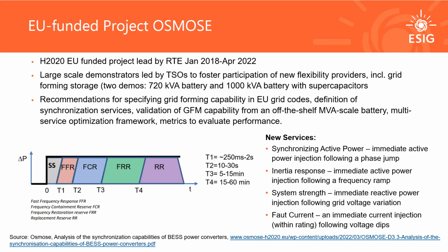Jumping to the EU-funded project OSMOSE, they also have specifications for grid forming, on a plant level. But I think what's interesting here is that they identified what they call synchronization services. These are some of the services that are currently provided by synchronous generators and will no longer be there when synchronous generators retire. These services can be provided by grid forming inverters and remaining synchronous generators. This is the gray area on the left-hand side figure. Everything on the right-hand side is currently provided either by synchronous generators or grid following inverters, and these are all frequency services.